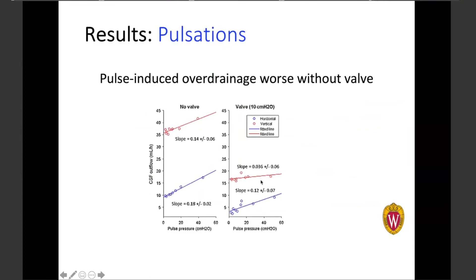And finally, when we looked at compliance of the pseudoventricle, we found that at low compliance, higher pulse wave increases drainage even more. So imagine those children or now adults who've been shunted since they were babies, and therefore they have no compliance. You've basically dried out their brain. The brain is like a rock. Every pulse wave that happens is gonna drive pretty much all the fluid down the shunt system, and this is why they're so susceptible to weather changes and to activity and movement and all of that stuff. So the bottom line is that compliance does not affect drainage directly, but the lower the compliance, the more significant the effect of pulse pressures on drainage.